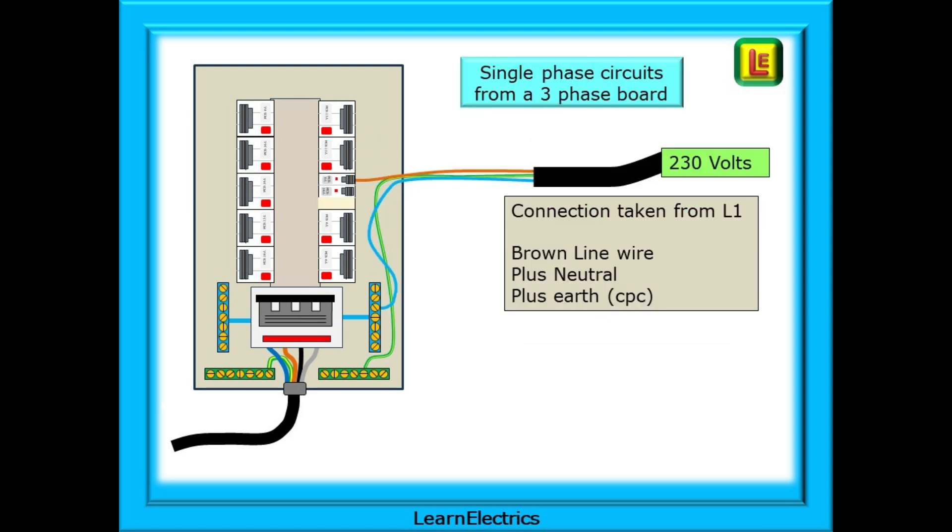We can also run single-phase 230 volt circuits. We will simply replace a three-phase breaker with single-phase breakers and connect a line to the breaker, a neutral wire to the neutral bar and an earth or CPC to the earth bar. It is not good working practice to run a single-phase circuit from a three-phase breaker. If it's a single-phase circuit, install a single-phase breaker.